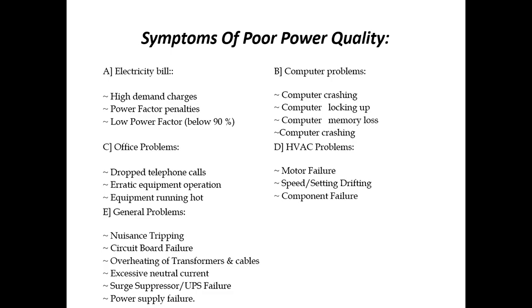If poor power quality is given by the sources, you get computer problems: sometimes the computer crashing, sometimes the computer locking up, sometimes computer memory loss. Then office problems, if you work in any office: dropped telephone calls, erratic equipment operation, some noises, equipment running hot. Even if there is no load on the motor, it still shows hot when running. Then HVAC problems, that is heating, ventilation and air cooling problems. Sometimes you get motor failure, speed setting drifting, component failure. So all these are symptoms of poor power quality.